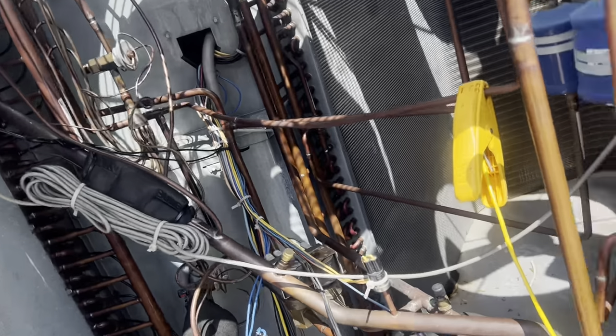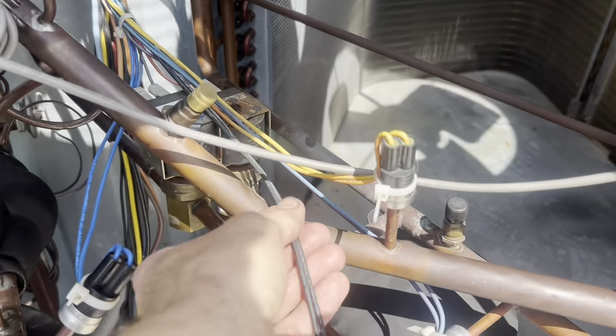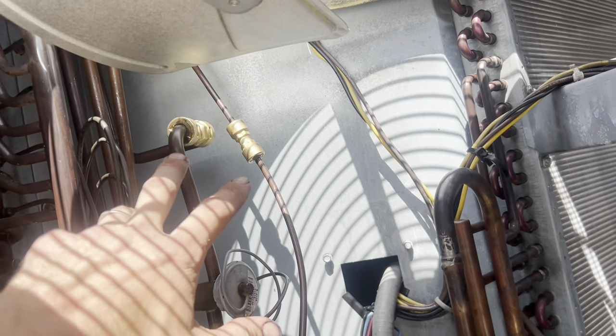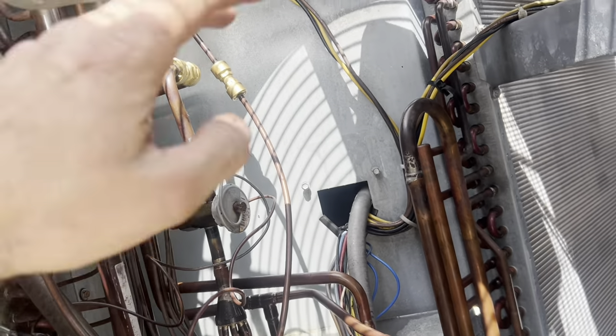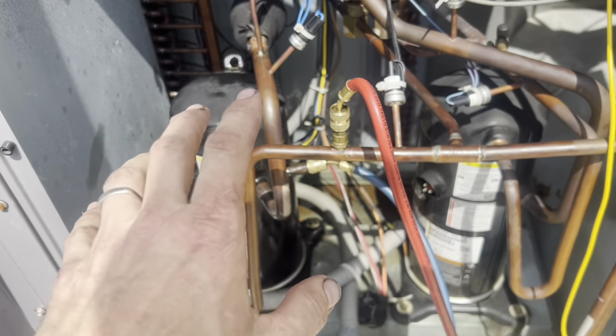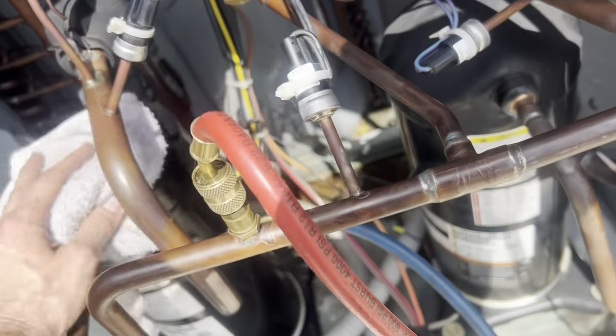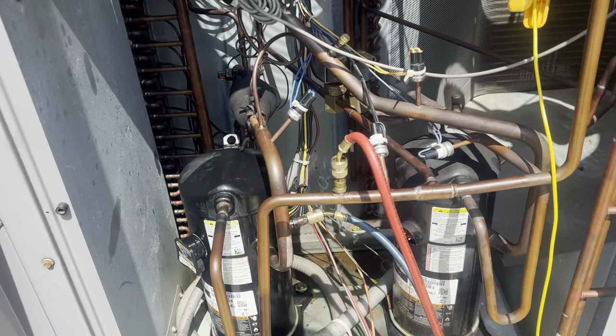It's been all sorts of crazy and they didn't have AC in the dining room. There are possible rub-outs everywhere, but we've repaired the problems that were actual problems. Pressure tested, leak tested, vacuum tested, evacuated, and charged the system — almost. I still need three more pounds of gas. I emptied the two bottles I had in my van and I've got somebody picking me up a new bottle. I've got about 26 pounds in first stage.